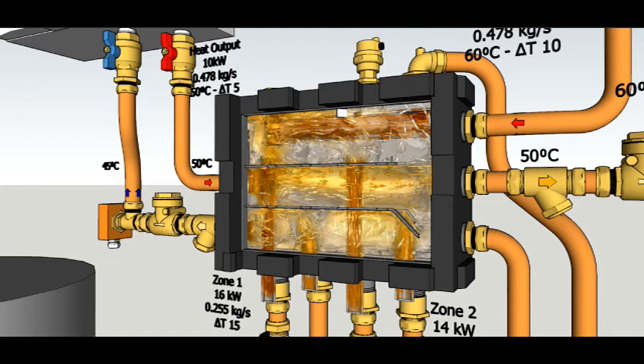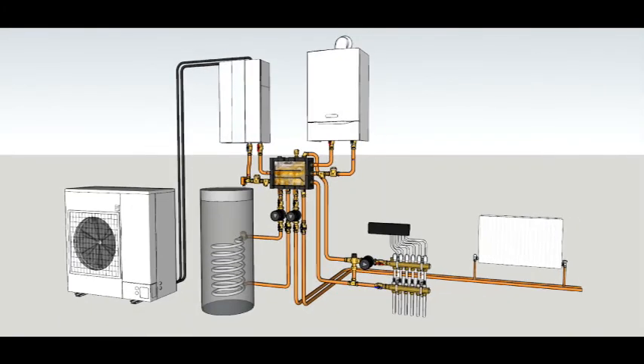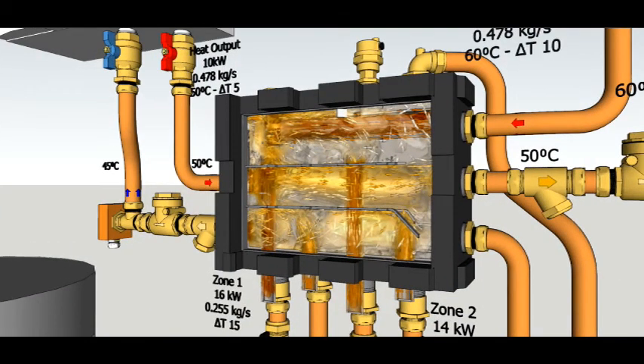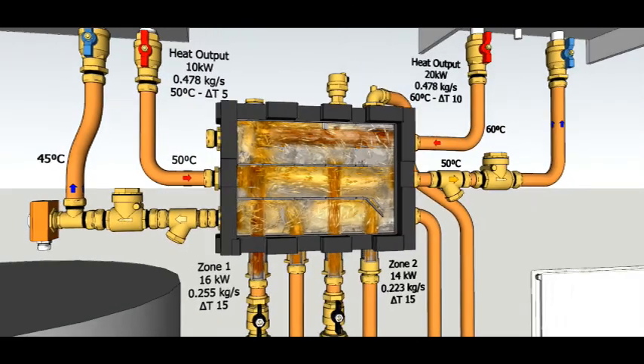The heat pump takes the 45 degree water, brings it up to 50 - that's transferred across the middle of the bypass chamber and is introduced directly into the gas boiler return. In turn, the gas boiler takes it up to its exchanger, raises it to 60 degrees and delivers it back into the energy zone manifold at the top right hand corner, where it travels through the internal pipe and heads from left to right across the flow chamber. The two heating circuits - the hot water cylinder and radiators - are designed to have a 15 degree temperature drop across them. With the 15 degrees dropped from the 60 degree flow, we now have return water coming back into the return bottom chamber which is 45 degrees. That 45 degrees then heads off on its journey back through the heat pump, heated across the middle chamber into the gas boiler, heated to 60, and it heads off again.